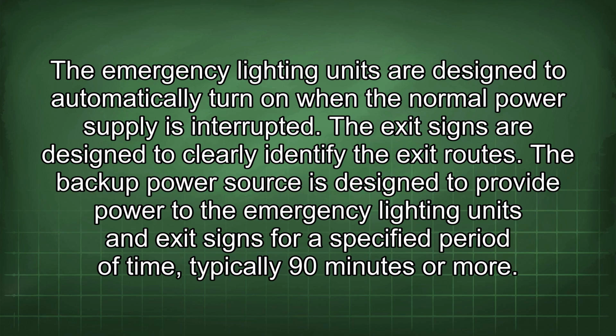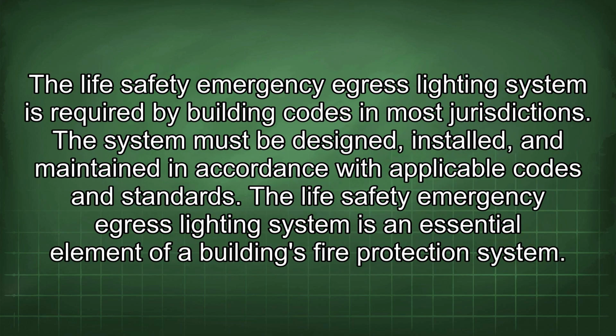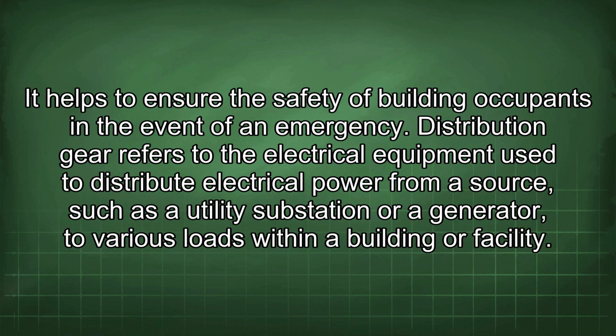The exit signs are designed to clearly identify the exit routes. The backup power source is designed to provide power to the emergency lighting units and exit signs for a specified period of time, typically 90 minutes or more. The life safety emergency egress lighting system is required by building codes in most jurisdictions. The system must be designed, installed, and maintained in accordance with applicable codes and standards. The life safety emergency egress lighting system is an essential element of a building's fire protection system. It helps to ensure the safety of building occupants in the event of an emergency.